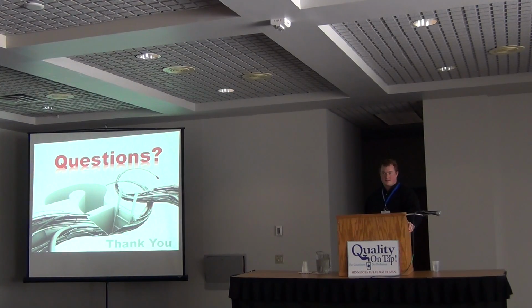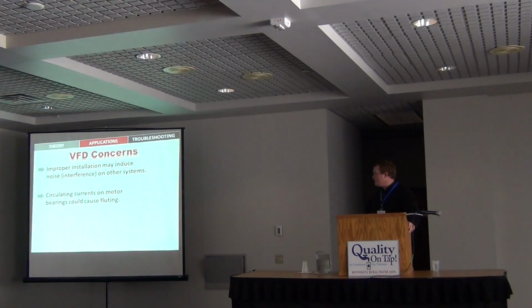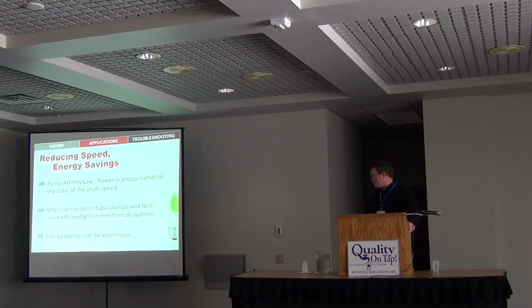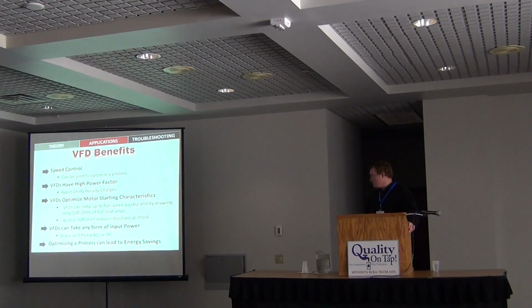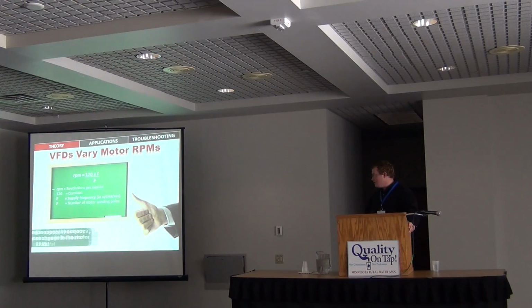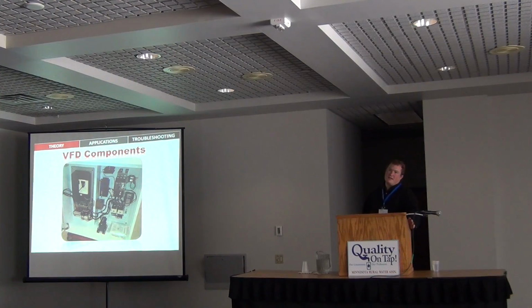So what are your thoughts on preventive maintenance? Do we need to look at this yearly, every 5 years, only when it's broken? Within the VFD enclosure itself, I have a company I've dealt with in the past, and they just called me again the other day and said, "Do you have any VFDs you'd like cleaned, looked at, inspected?" Is it really a need, or should it be done annually, or every 5 years, depending upon the enclosure? Let's say it's in a panel, a lift station panel, or in a building, a pretty clean atmosphere.